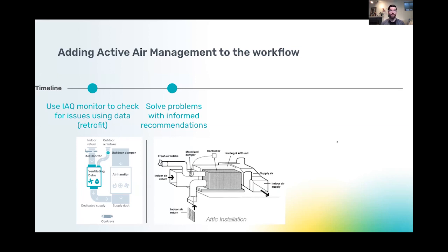Part of that can be done through looking at the runtime. How frequent is the system running? What do the heating and cooling cycles look like? How long do they last? A properly sized piece of equipment should run fairly long periods of time to distribute that hot or cold air and establish a mean radiant temperature of the objects in the home. And because it's running longer, you're getting more filtration time and more circulation inside of the home.